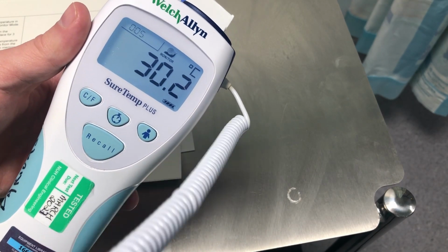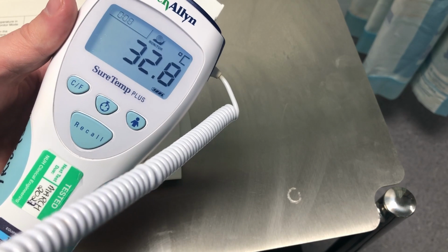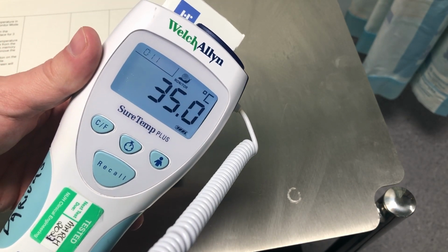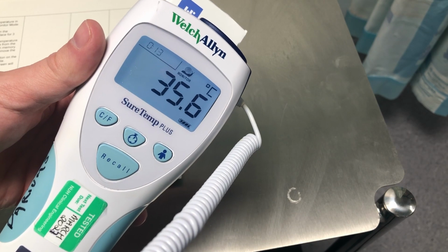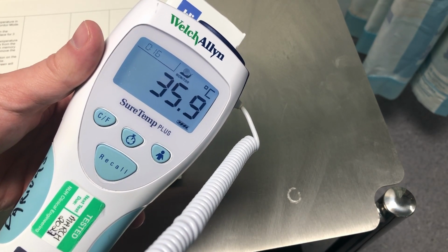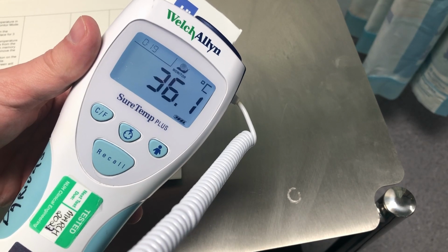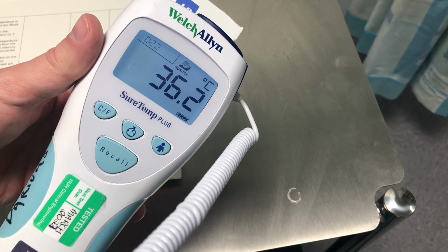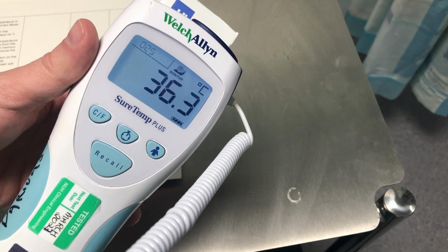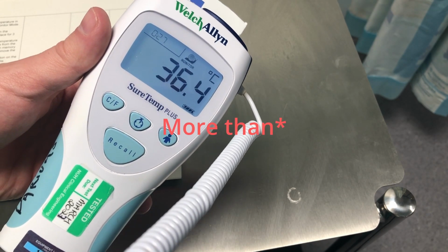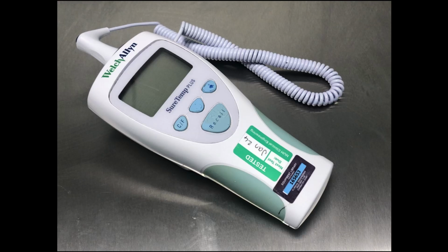Monitored temperatures are not stored in the memory for recall, and they are taken very similarly to the typical oral and axilla temperatures. You will just leave the probe in place for 3 minutes in the sublingual pocket of the mouth, or 5 minutes in the axilla with good skin contact. Beyond 3 to 5 minutes is not recommended in any mode. Record the temperature before removing the probe from the site, and then when you are finished, eject the probe as previously shown. The temperature range of the device is 30 degrees Celsius to 43 degrees Celsius.